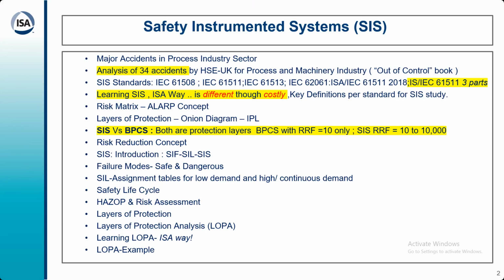Why I'm telling you this is because most of the chemical, petrochemical and process industries in India, including pharma, do not go beyond BPCS, that is DCS based or PLC based or single loop controller based, or whatever way they are deploying. But in HAZOP also, they go on adding additional transmitters, adding additional safety shutdown valves in BPCS. Now, this is where I think a little more focus will be required, and I'll try to elaborate in the presentation.